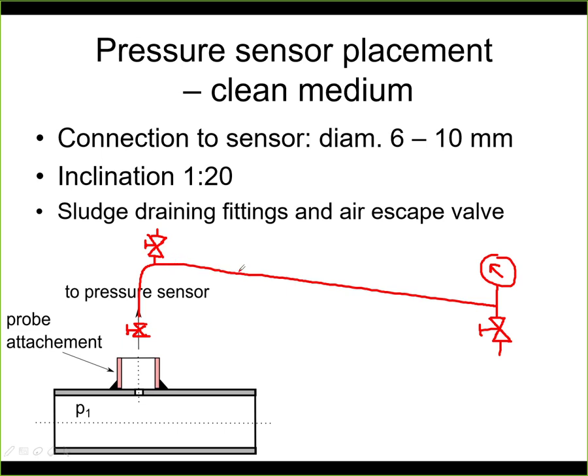Now it's important to make an inclination here on this pipe. This inclination is typically about 1 to 20 ratio. And here on the highest place on this system, you need to place a valve where you can escape the air. Eventually, if this is a liquid, for example, then there might be bubbles, and those bubbles will fill this system. Then you will have bubbles at the highest place, and your gauge will not measure properly. So this is the air escape valve. Now this valve is used to disconnect this whole system from this probe. So this valve is either fully open or fully closed, nothing in between. So it does not have an effect on the pressure because it's fully open.